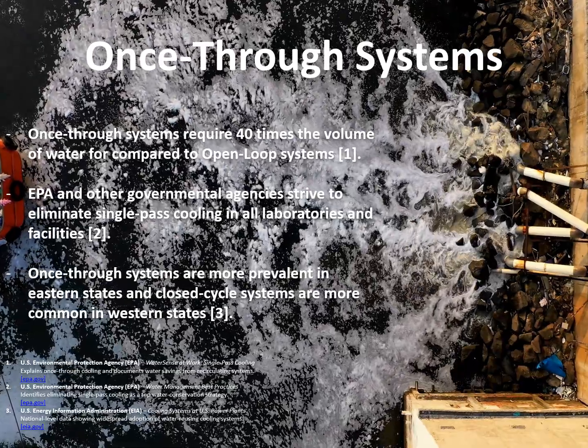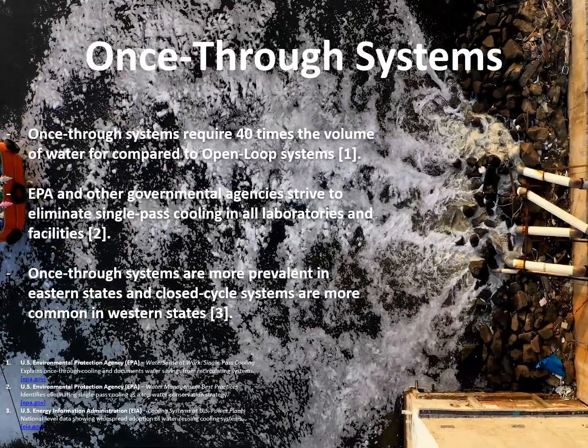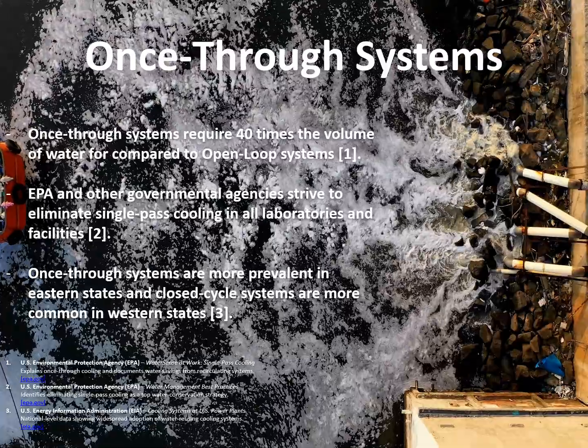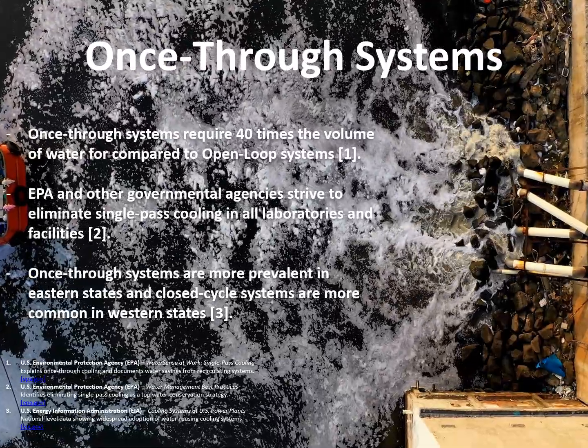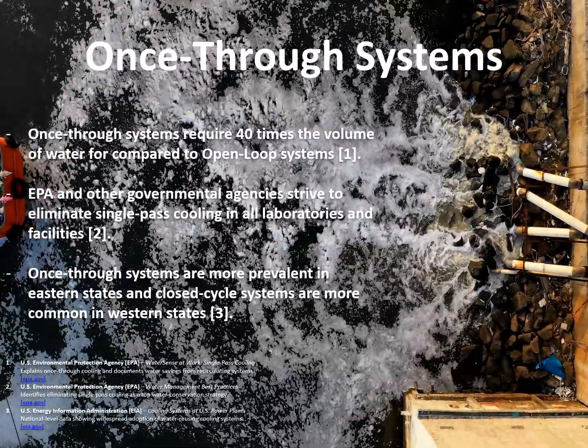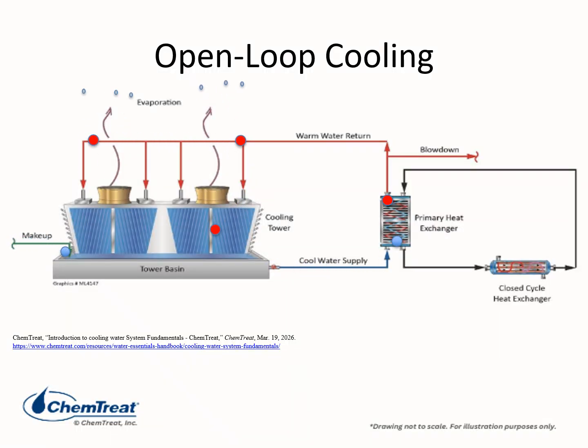They place enormous stress on local water bodies. They raise the river or stream temperatures, which can harm the ecosystems. And in drought-prone regions, they simply aren't sustainable. A second option for cooling is the open-loop cooling system. It allows the cooling water to be open and exposed directly to the air. The hot water returning from the heat exchanger is sprayed over fill media in a tower, while air is drawn through by large fans. A portion of the water evaporates, carrying heat away, and the remaining cooled water returns to the basin of the tower and is then pumped back through the system.